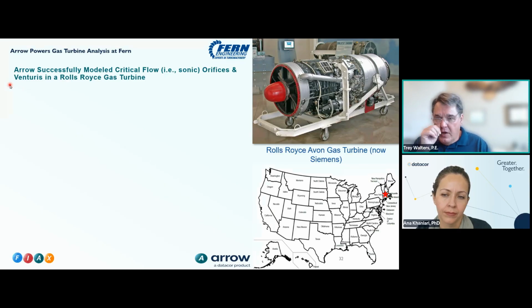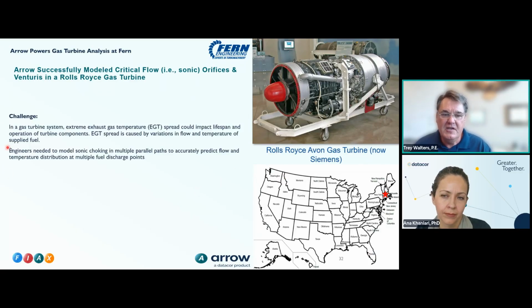And there are critical flow, sonically choked orifices and venturis. They were trying to model a Rolls-Royce Avon gas turbine at this time for power generation. This is now part of Siemens. The challenge is the gas turbine system EGT spread, exhaust gas temperature spread, could impact lifespan operation of turbine components. EGT spread is caused by variations in flow and temperature of supplied fuel. So what you really want to get, again, not an expert on this, but from talking to people who are, you want to get your delivery of your gas into your gas turbine as it goes into the injection points around the gas turbine.